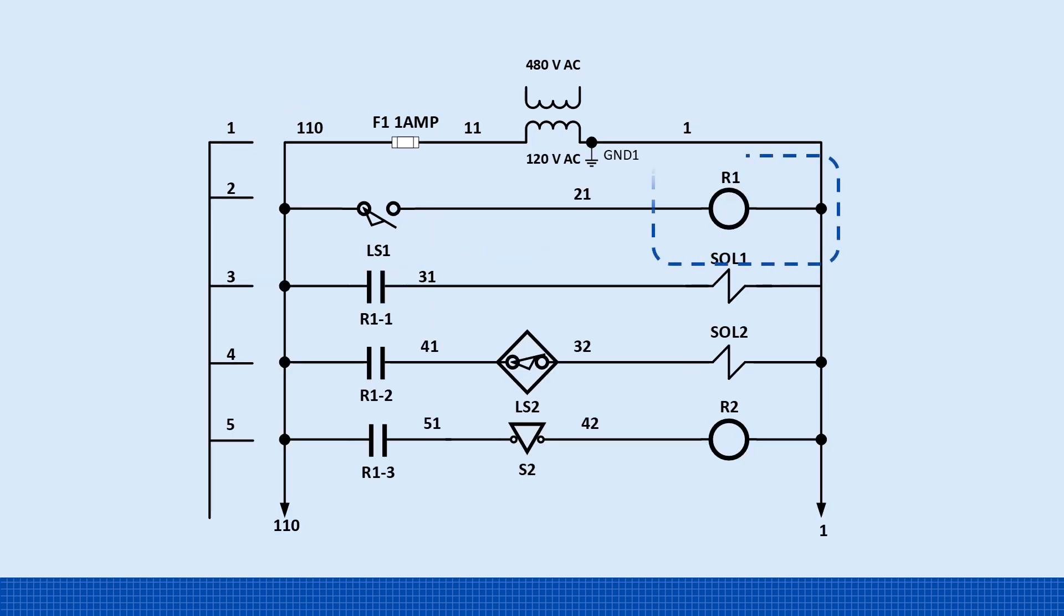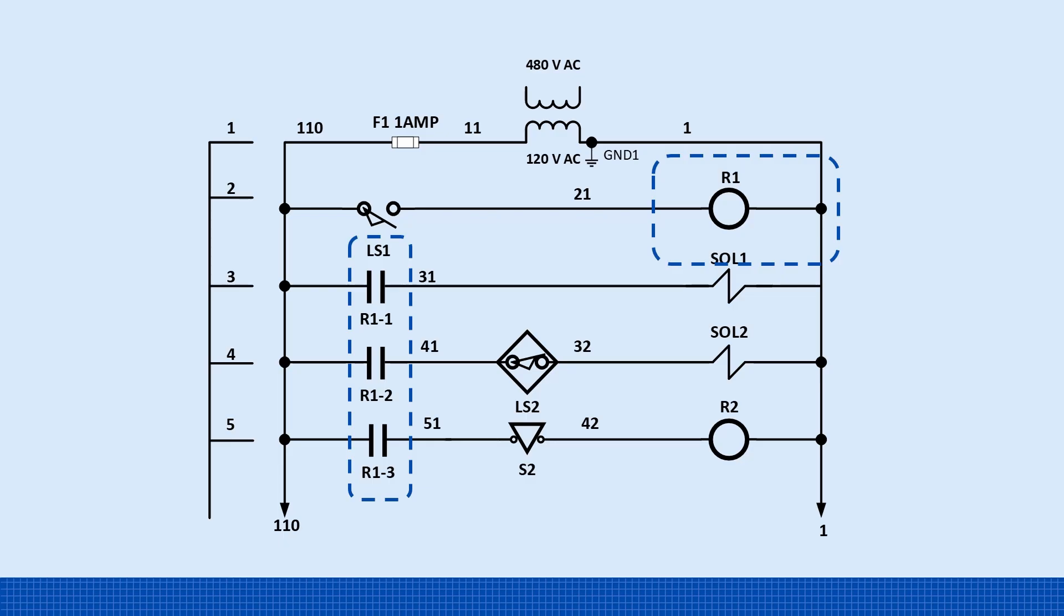A better design is to have limit switch LS1 energize a 3 PDT relay, labeled R1. Each of R1's three normally open contacts can then control solenoid 1, solenoid 2, and relay 2 individually. This approach keeps the schematic clean and organized. More importantly, LS1 no longer carries the combined current of all three loads, only the small coil current needed to energize R1.